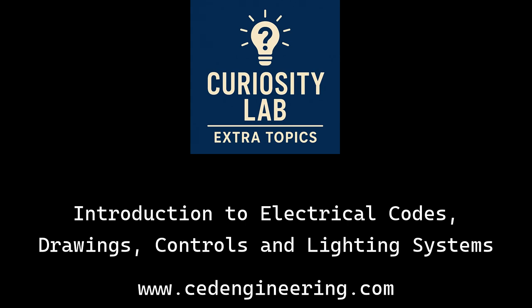Then there's bonding versus grounded. People mix these up all the time. Bonding is about physically connecting metal parts so they're all at the same electrical potential, like linking pipes and enclosures together. Grounding connects that whole bonded system to the earth or back to the power source. Bonding is a vital part of grounding, but you can't just use the earth itself as a bonding jumper. Its resistance is too high. Getting that distinction right ensures fault current takes the safe path back.